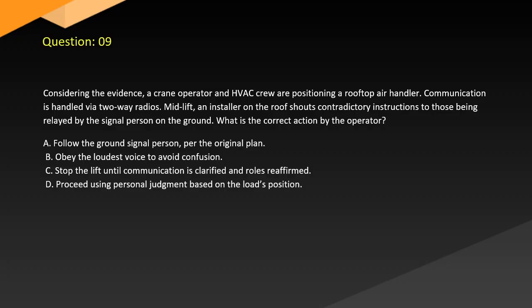Question 9. Considering the evidence, a crane operator and HVAC crew are positioning a rooftop air handler, and communication is handled via two-way radios. Mid-lift, an installer on the roof shouts contradictory instructions to those being relayed by the signal person on the ground. What is the correct action by the operator? A. Follow the ground signal person per the original plan. B. Obey the loudest voice to avoid confusion. C. Stop the lift until communication is clarified and roles reaffirmed. D. Proceed using personal judgment based on the load's position.